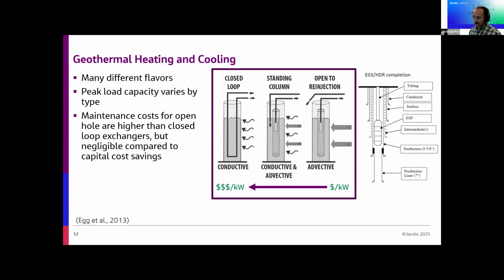For completions in unconsolidated zones, you may limit the total drilling depth, which is a fundamental challenge in urban environments or places with high demand densities, like campus energy systems, healthcare, or downtown districts. Considerations then turn more to the lithology you're going to encounter and how you're actually going to complete your bore field or well field in place to match the loads completely. Balancing these systems becomes pretty important if you don't have advective flow in the formation to wash away your thermal plume and renew it, because you can thermally saturate the system, increasing or depleting temperatures in the reservoir and reducing its overall lifetime.